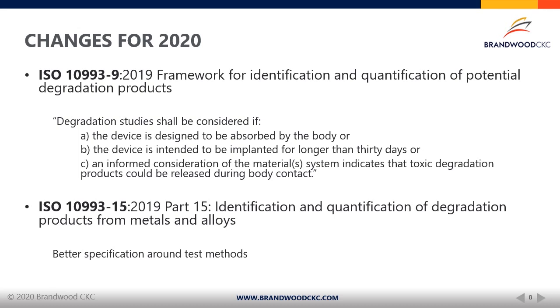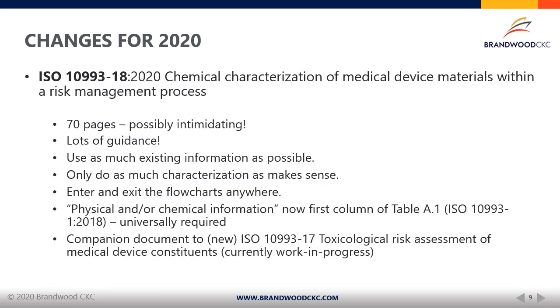Coincidental with the release of the Part 9 revision is the revision of Part 15, and Part 15 is all about the application of the principles in Part 9 as it relates to metal and alloy devices. The key improvements to Part 15 are around better specifications for the test methods in producing and identifying degradation products. A big change in the 10993 series of standards has been the revision of Part 18, which is chemical characterization of medical device materials.